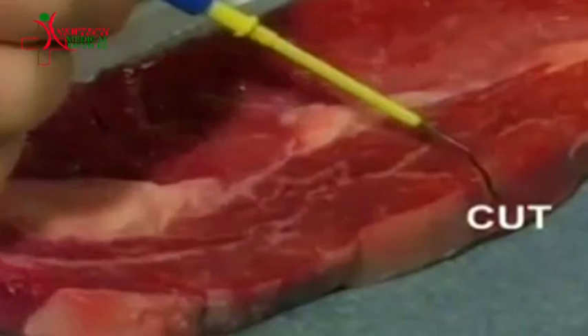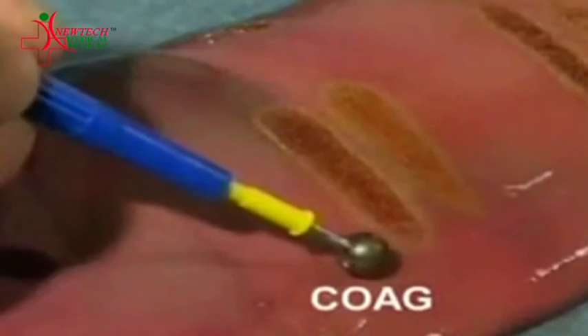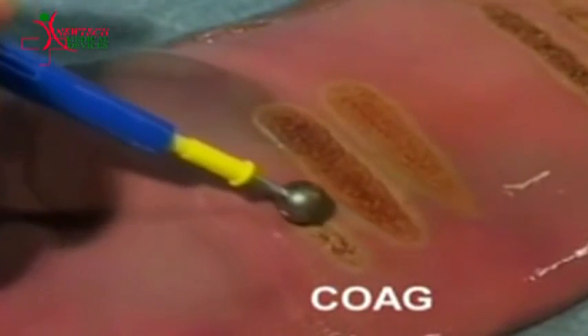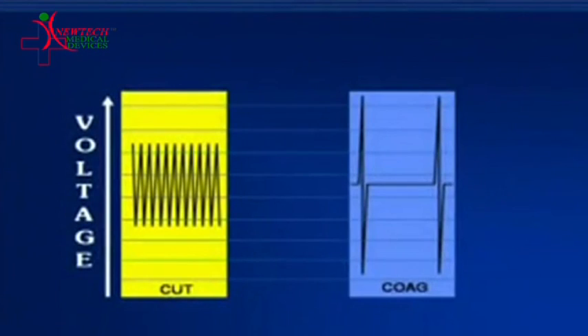A cautery pencil is used to cut and coagulate at the same time. The difference lies in the peak voltage and the frequency of the alternating current supplied through it.